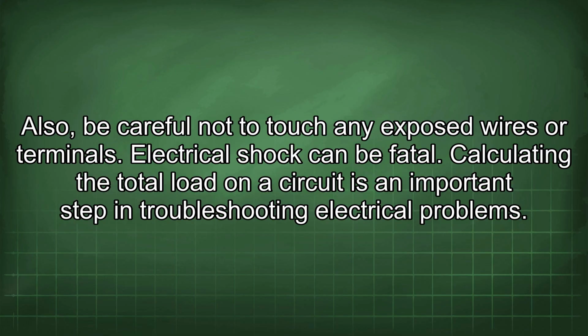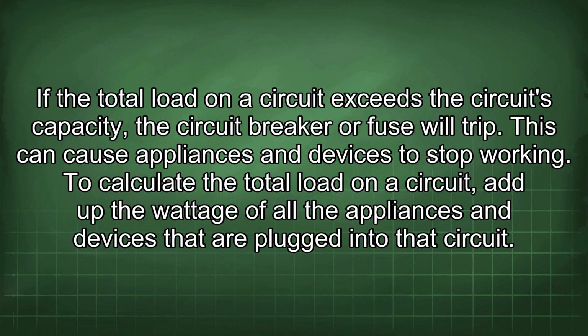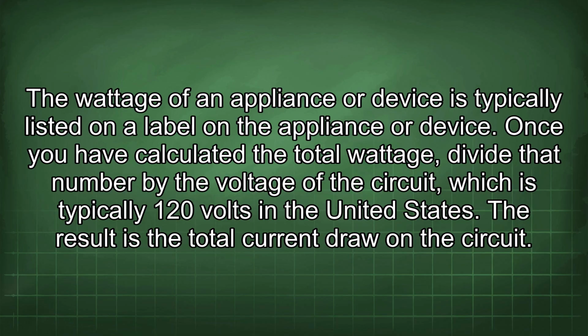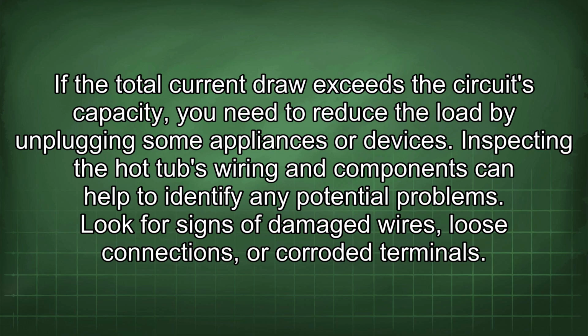Calculating the total load on a circuit is an important step in troubleshooting electrical problems. If the total load on a circuit exceeds the circuit's capacity, the circuit breaker or fuse will trip. This can cause appliances and devices to stop working. To calculate the total load on a circuit, add up the wattage of all the appliances and devices that are plugged into that circuit. The wattage of an appliance or device is typically listed on a label on the appliance or device. Once you have calculated the total wattage, divide that number by the voltage of the circuit, which is typically 120 volts in the United States. The result is the total current draw on the circuit. If the total current draw exceeds the circuit's capacity, you need to reduce the load by unplugging some appliances or devices.